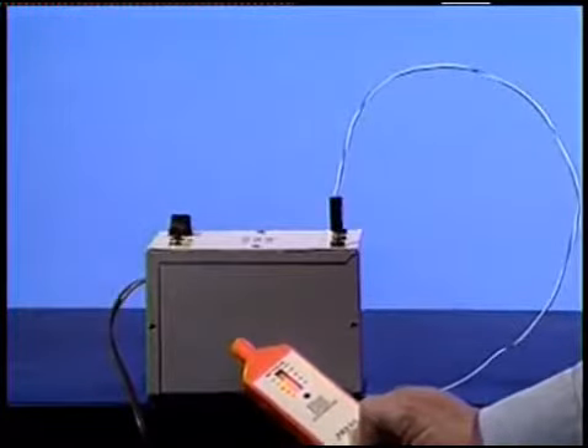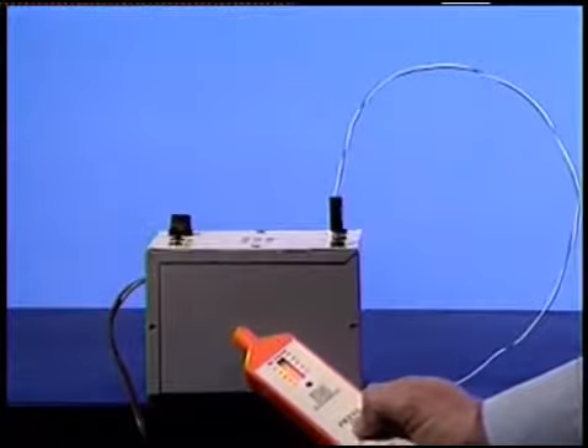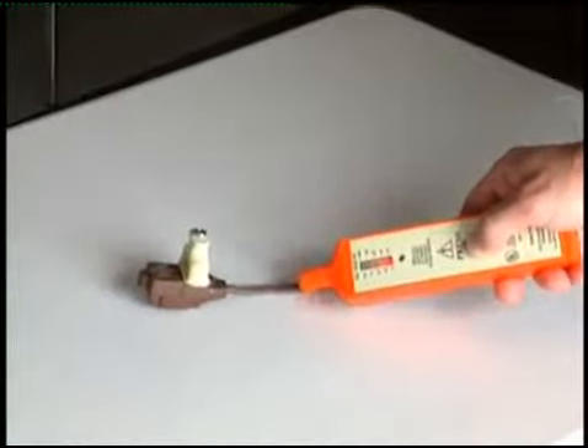Today, you will be shown a new test set for your use that will replace the voltage detector you are familiar with. The purpose for using the new test set is the same, a tool to detect the presence of commercial power hazards. With the new test set, which we will call the Foreign Voltage Detector, or F.V.D., contact is not required. It needs only to be in close proximity to the source. Detection through painted surfaces, even wire insulation, is now an easy task.